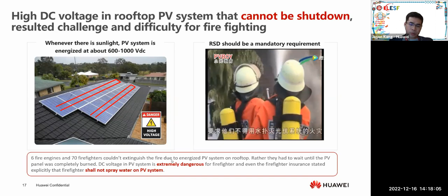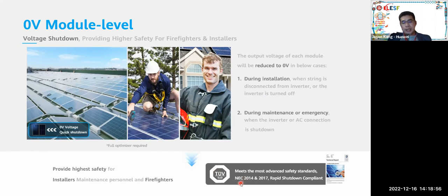Now with the optimizer installed, let me turn on my pointer again. When the inverter trips, if there's a maintenance or emergency, or during installation, the output voltage of the PV module, instead of having 600 to 1000 volt DC, for example, can be reduced to 0 volt. So that's the technology that we provide, and it's very safe for the O&M personnel as well as the firefighters to be on top of the roof, if you have a full optimizer installed for the PV system. This rapid shutdown capability of ours using optimizer complies with the NEC standard and also the German standard as well.